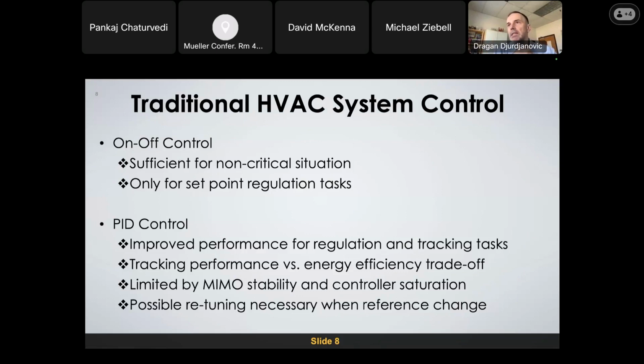I will give you an example from my colleague, who works at a company that builds data centers. In one of the earliest examples, maybe 5-6 years ago, they were called by a customer who was complaining about the vents shutting down and opening up, because the control mechanism was basically on-off control, where they would open the vents when they needed to cool the data center, and close them when the temperature had cooled off. It was actually in the Pacific Northwest where this was happening.